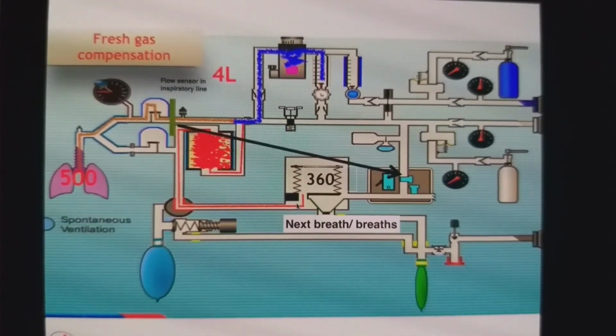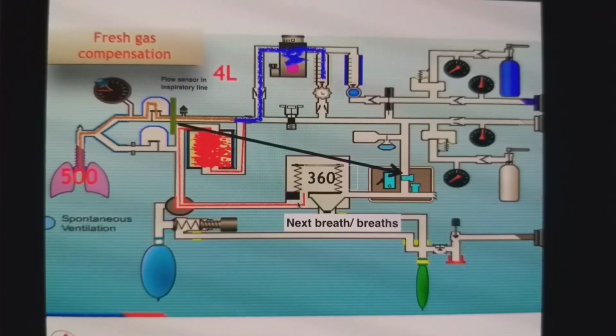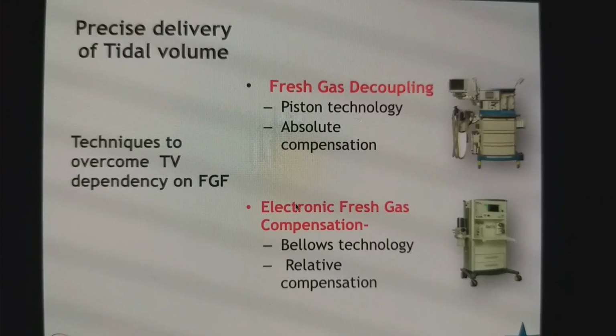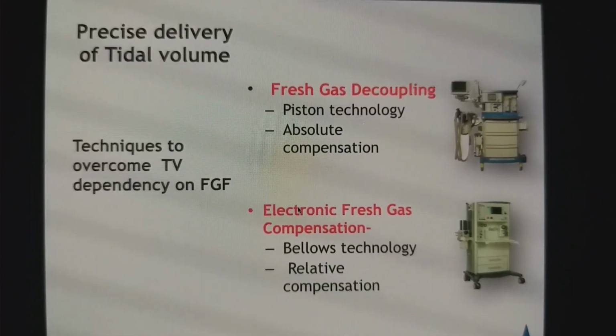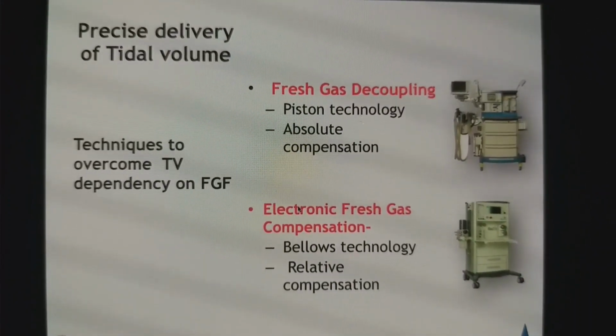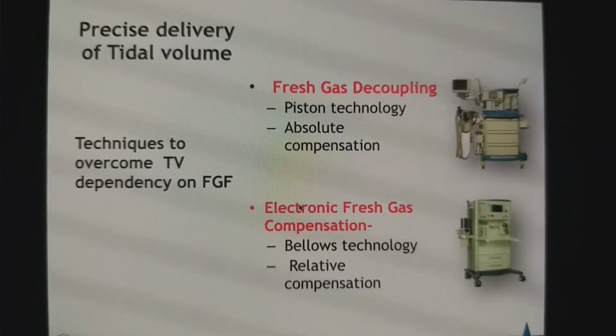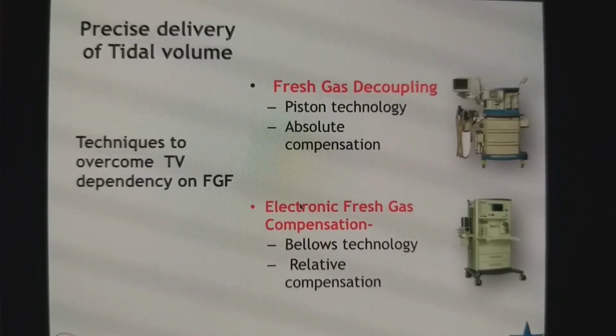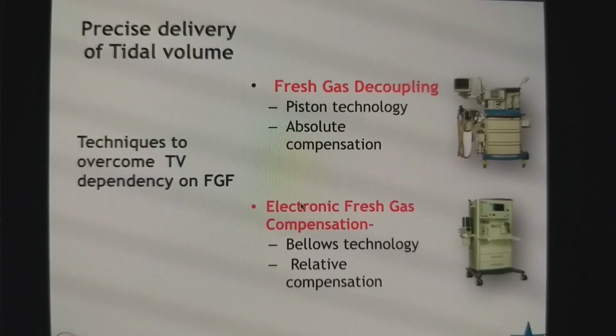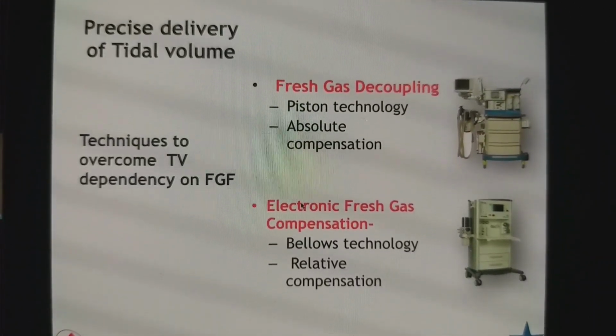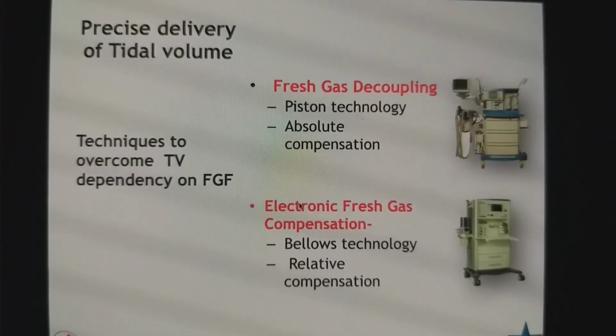So there are two technologies. One is called the decoupling mechanism. The second is called fresh gas compensation. So precise delivery of tidal volume by the majority of anesthesia machines is done by these two techniques. One is fresh gas decoupling, which is a piston technology. Here the compensation is absolute. There is no mixing of fresh gas flow with the inspired flow.